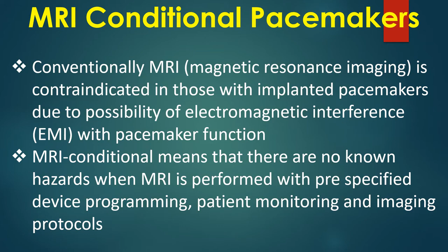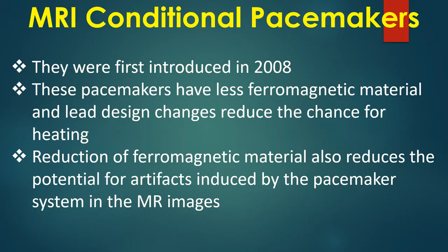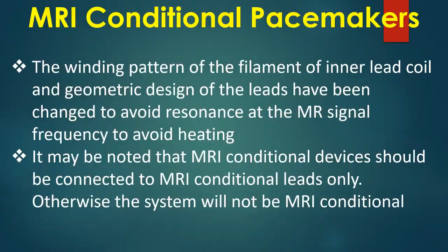These pacemakers have less ferromagnetic material and lead design changes reduce the chance for heating. Reduction of ferromagnetic material also reduces the potential for artifacts induced by the pacemaker system in the MR images. The winding pattern of the filament of inner lead coil and geometric design of the leads have been changed to avoid resonance at the MR signal frequency to avoid heating. It may be noted that MRI conditional devices should be connected to MRI conditional leads only. Otherwise, the system will not be MRI conditional.